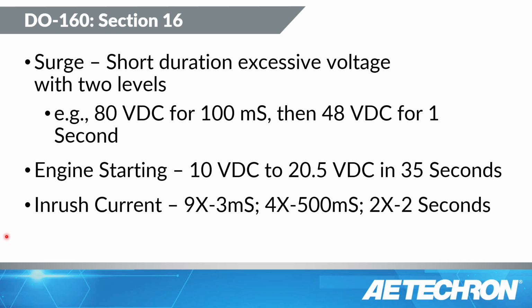That means the ramp up for, say, DC can be up to 300 microseconds, and for AC it can be a quarter cycle. Well, for 400 hertz, that's 625 microseconds. The reason I point that out is that if you do have internal capacitance, which typically is the source of the inrush, it's the capacitors charging up when you turn on. Having a ramp up time will allow those capacitors to charge a little bit slower and might give you a chance to pass that 9x, 9 times the maximum input current, within that 3 millisecond window.